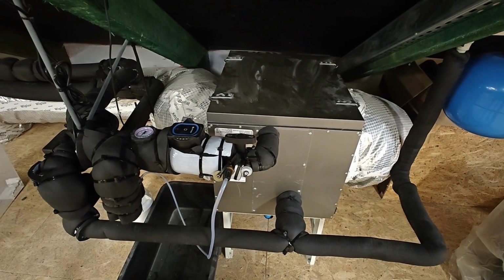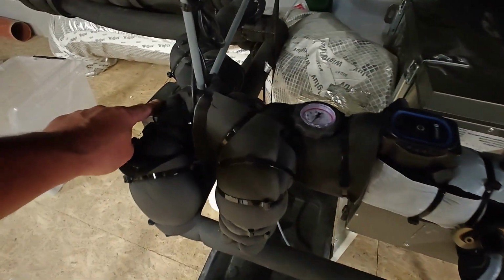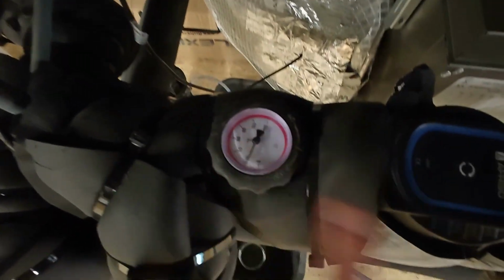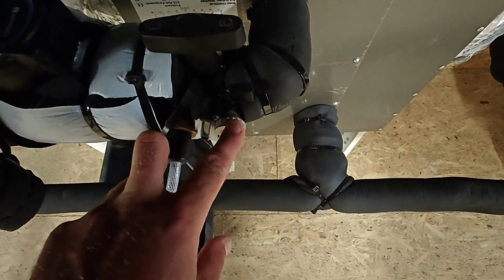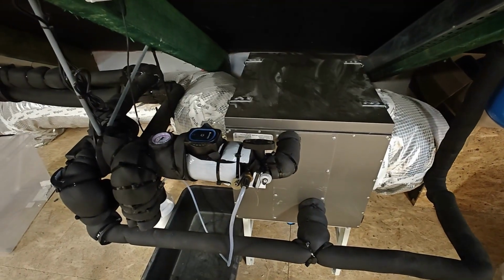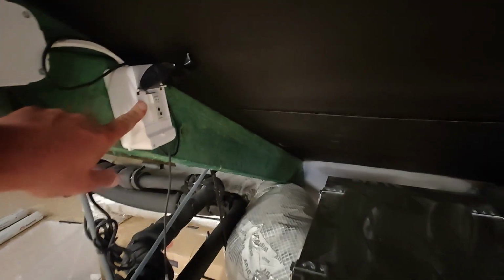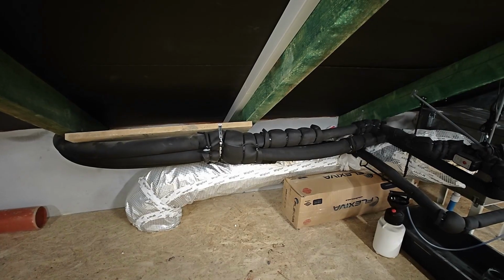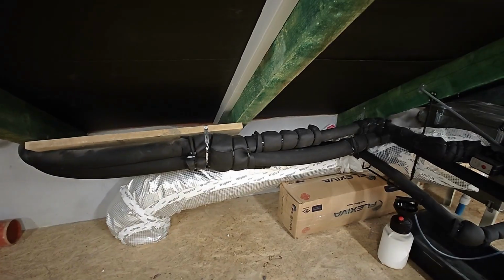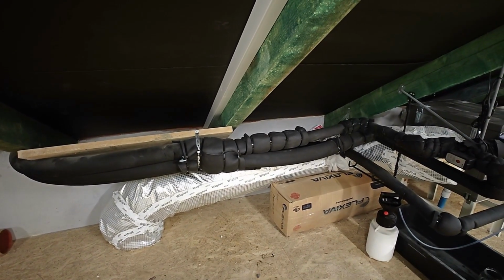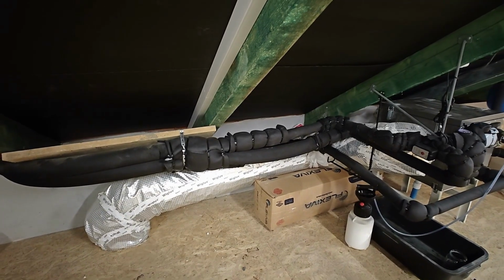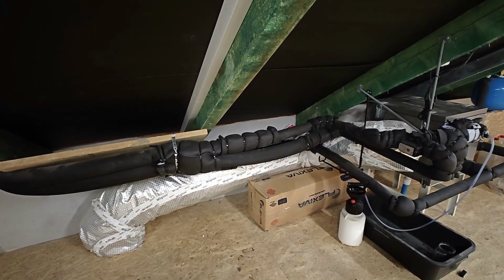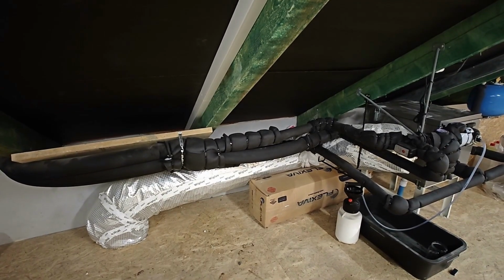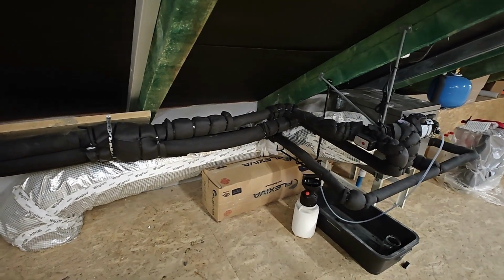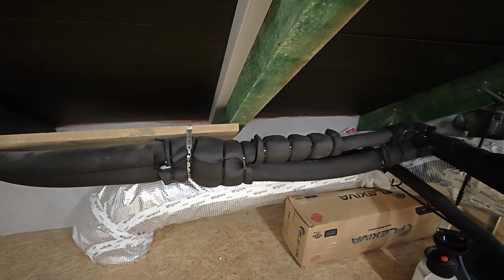Before the GWC exchanger, there is a switching module consisting of an actuator that is positioned at this moment, a temperature sensor, a circulation pump, and 2 valves that allow for filling and draining the system. The relay I mentioned earlier handles the individual loop switching. It's placed here. We transition from PE water pipes to brass. For the supply and return, I used welded PP pipe because of its tightness and no glycol leakage, which has highly penetrating properties. Furthermore, there is no electrochemical corrosion, which would happen if galvanized components were used. The entire system is very well insulated because initially when the pipes weren't insulated, there was a lot of condensation.